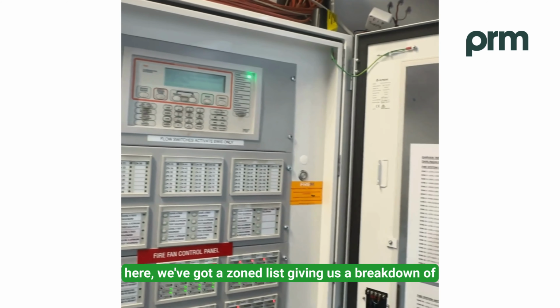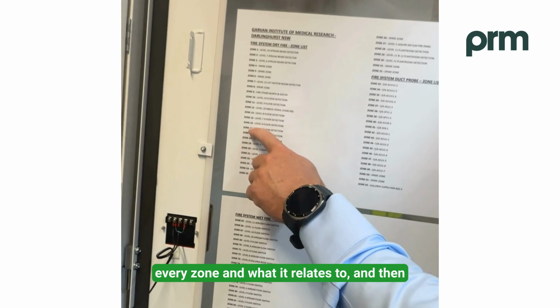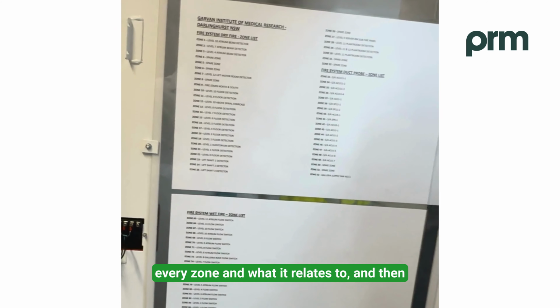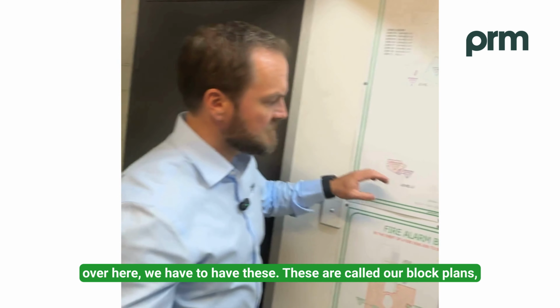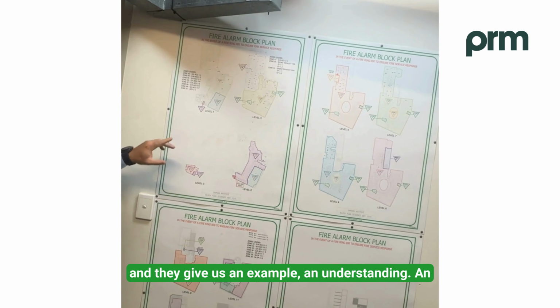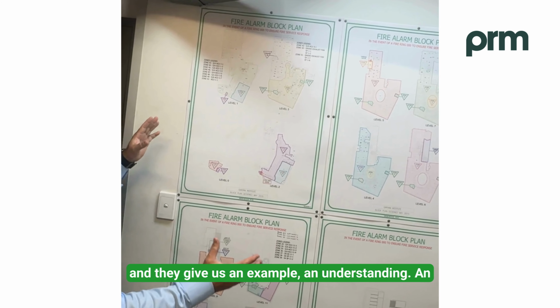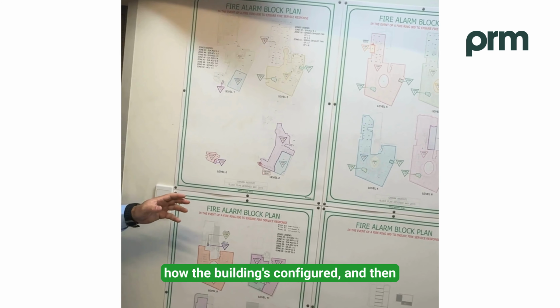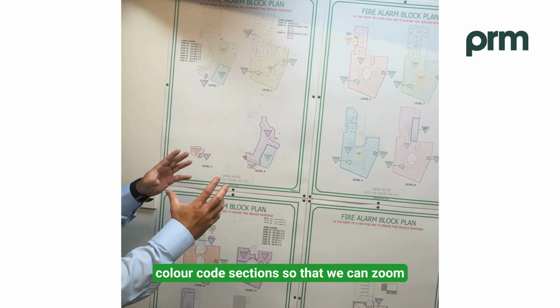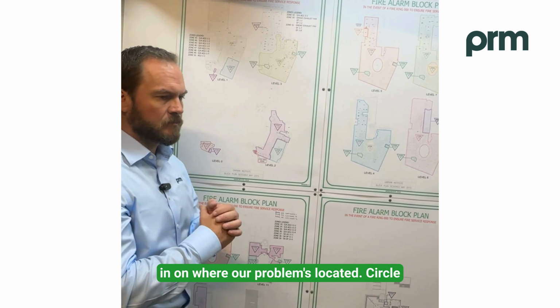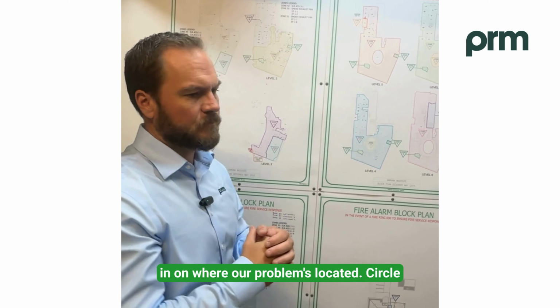Over here, we've got a zoned list giving us a breakdown of every zone and what it relates to. And then over here, we have to have these. These are called our block plans. And they give us an understanding of how the building's configured, and then color code sections so that we can zoom in on where our problem's located.